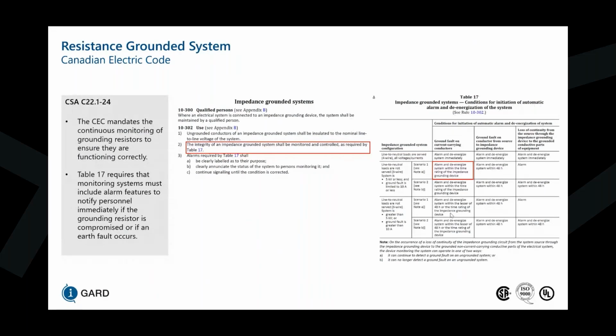Now, when it comes to the short circuit scenario for both rows, it says to alarm and de-energize the system within 48 hours. And for the open circuit condition, we either alarm if we can still detect a ground fault in an ungrounded system, or we alarm and de-energize the system within 48 hours if we cannot.